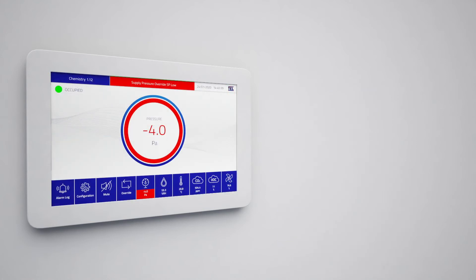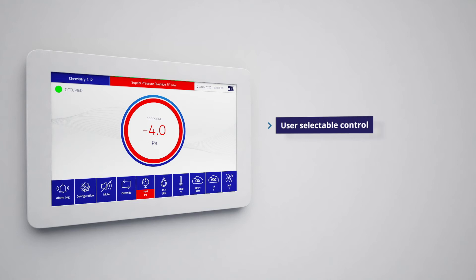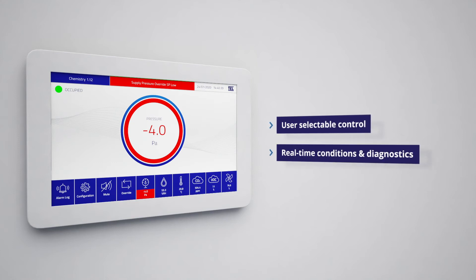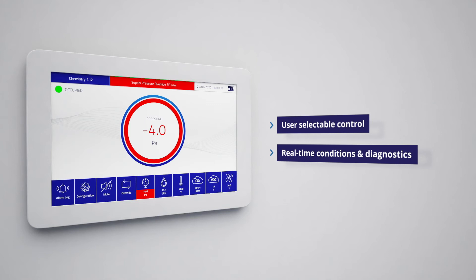In pressure mode, incoming air supply is controlled by changes in room pressure conditions as well as user selectable control and trending of humidity, temperature, CO2 levels and VOC levels. Alarm conditions and diagnostics are shown clearly in real time.